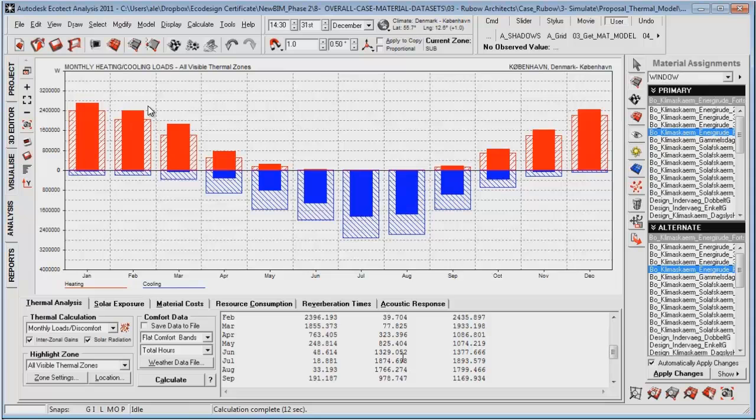As you see, I also increased my heating loads in the winter period, which can seem strange, but because cooling is more expensive and a lot of the time in relation to the comfort of the building, this is really what I'm looking for. So having a small amount more heating during the winter because of the lesser helpful heat gain in that period is really not what I was looking at here.